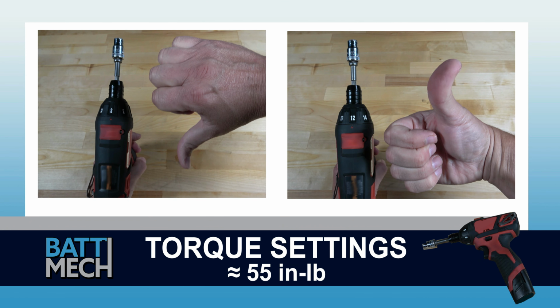Before attaching the wire harness, be sure your torque wrench is set to about 55 inch-pounds. If you don't follow these torque settings, you are likely to damage the terminals on the modules and will void your warranty. Never use max drill settings and never use an impact wrench.